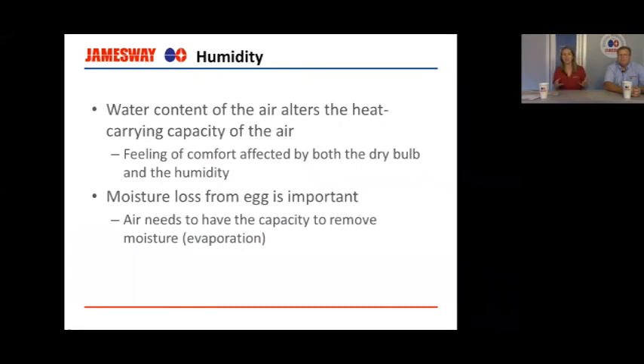But what is the big deal with humidity anyways? The water content of the air actually changes the heat carrying capacity of the air. And our feeling of comfort is affected by both the dry bulb and the humidity. And you hear that a lot here. People will say, I went to Arizona, it was so hot, but it was so dry and I was so comfortable. Where they're in New York, they're in Toronto, they're in Chicago during our very humid weeks that aren't nearly as hot as Arizona. But the humidity makes it feel so much hotter, right?